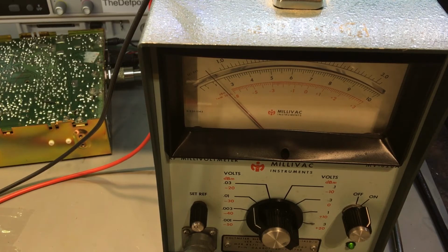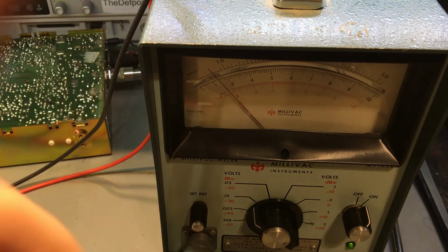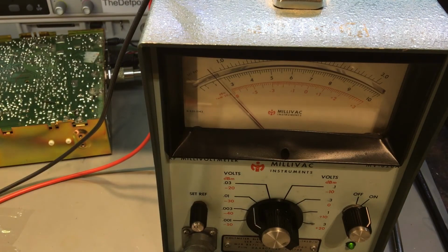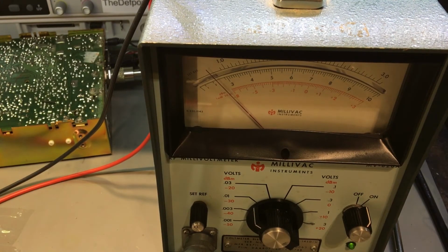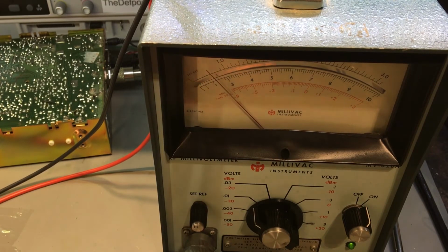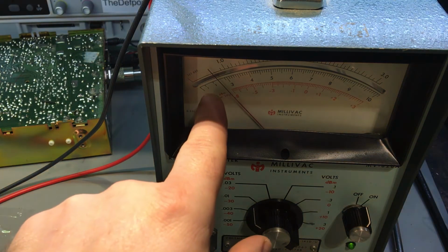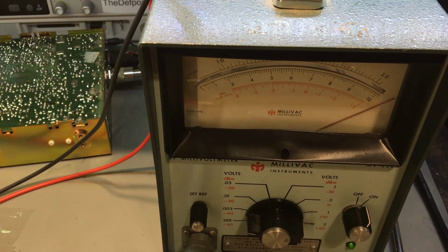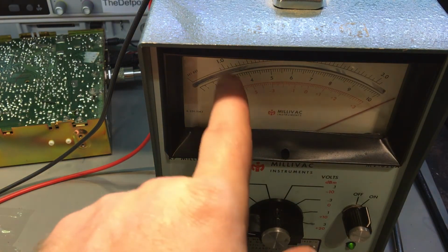Let's try a different frequency, let's try 10 kilohertz. Yeah, it's not liking that frequency. So I'm doing 10 kilohertz on my Marconi, the Fluke's saying that's 1 millivolt output, and yeah, that's right. I've got to set 1 millivolt, so that's okay there. But this is still not quite right, but then it's right at the bottom of the range, so it should be there. But this range here is just maxing out. Now, at 1 millivolt, it should only be about here. So it's got an issue there.